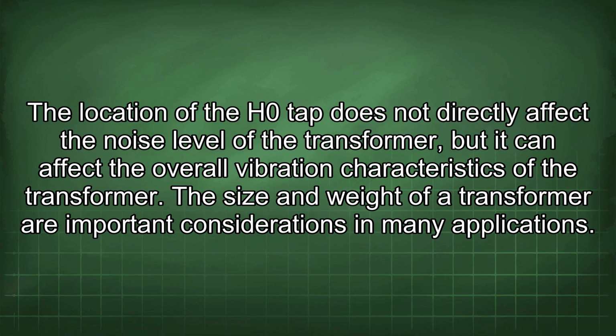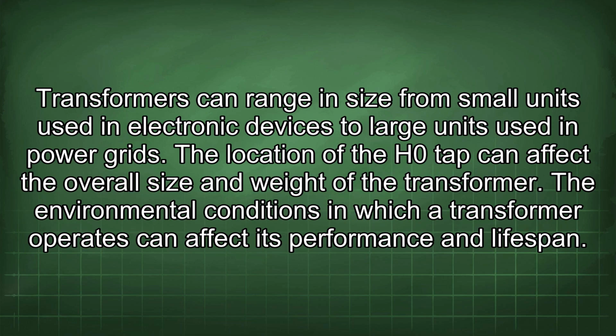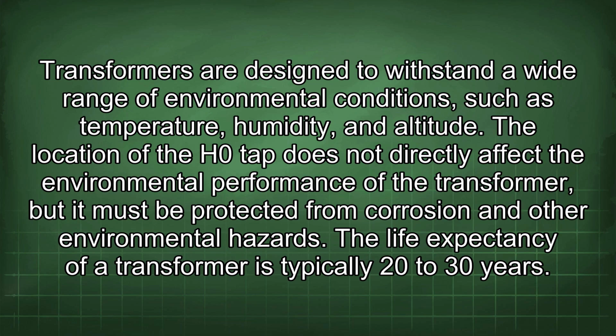The size and weight of a transformer are important considerations in many applications. Transformers can range in size from small units used in electronic devices to large units used in power grids. The location of the H0 tap can affect the overall size and weight of the transformer. The environmental conditions in which a transformer operates can affect its performance and lifespan. Transformers are designed to withstand a wide range of environmental conditions such as temperature, humidity, and altitude. The location of the H0 tap does not directly affect the environmental performance of the transformer, but it must be protected from corrosion and other environmental hazards.